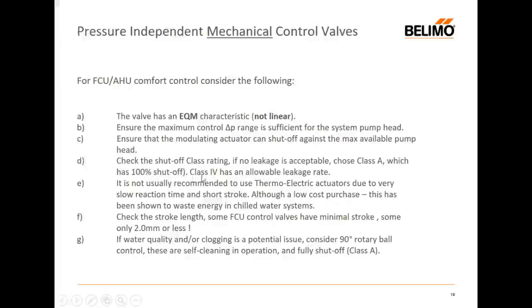And if we're happy to accept an allowable leakage rate, then we can accept class 4 or even class 5. It is not usually recommended, and I certainly wouldn't recommend, the use of a thermoelectric actuator, because they have very, very slow reaction times and usually a very short stroke. And here, this is a kind of valve where there's a wax element encased above the actuator and it is heated and it expands, and that provides the movement of the valve.